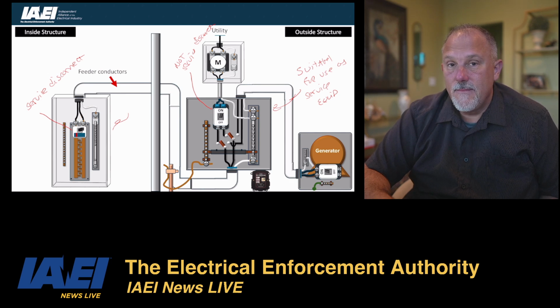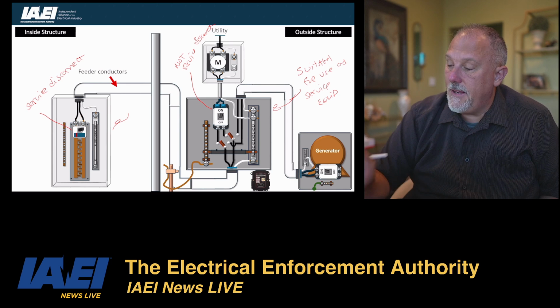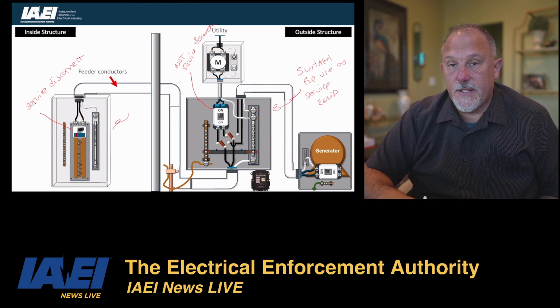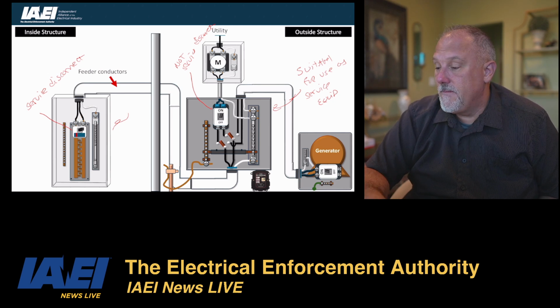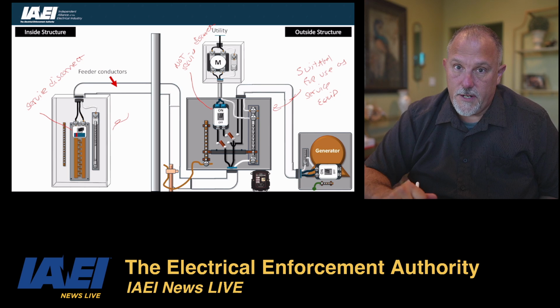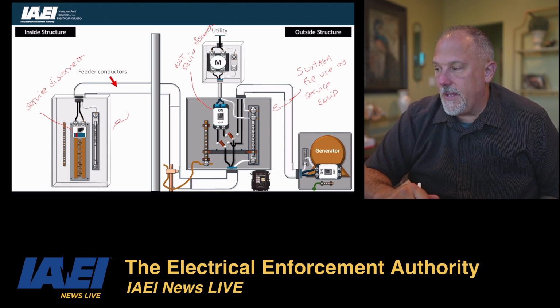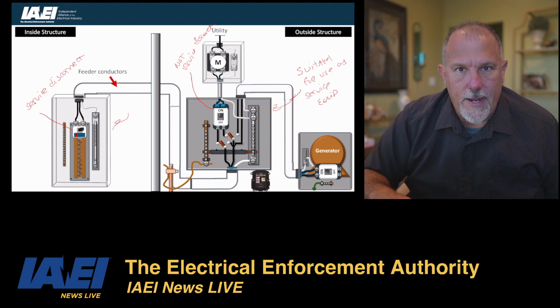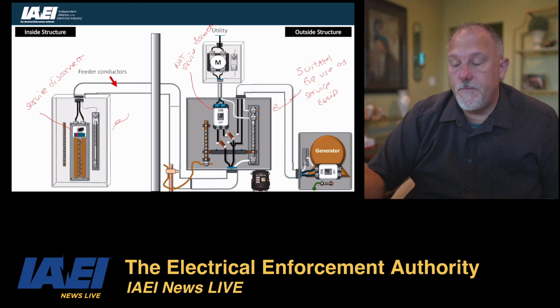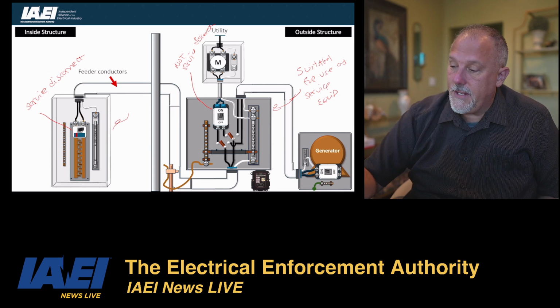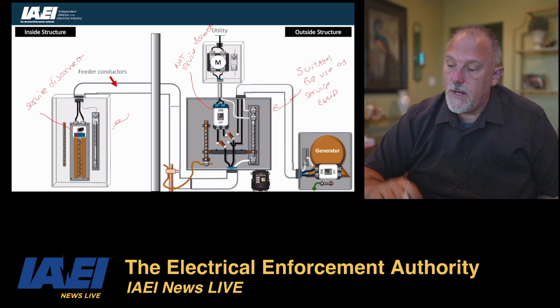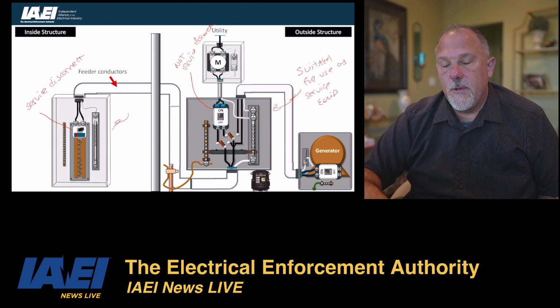But that breaker that's in that transfer switch is a service disconnect because it disconnects service conductors. And the breaker that's in that downstream panel board is not a service disconnect because it is disconnecting feeder conductors, not service conductors. So I don't think where I wanted to go with that is doable. At least I don't know a way to make the language make sense. I know what I want.